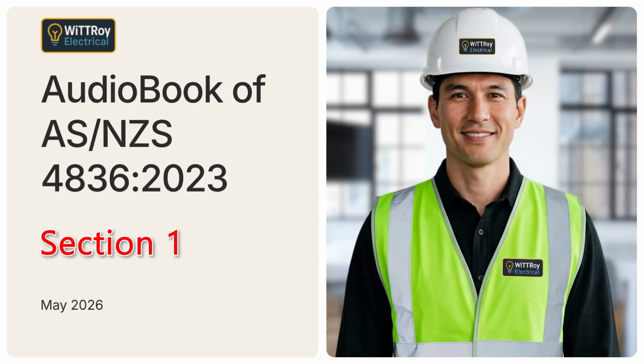Clause 1.4.19. Energized. Energized means connected to a source of electrical supply or affected by hazardous induced or capacitive voltages. This means a part can be dangerous even if it is not directly connected in the way we first expect. Induced voltage and stored or capacitive voltage must also be considered.